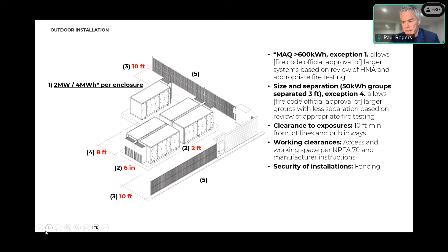And then as you can see, number five there is just showing a fence that is 10 feet. Now, I know there are some areas that have zoning, so the fence size should be based on your local zoning. But they want them at least 10 feet from the actual wall. They can go further than that based on what the code officials say, and they can back that up by using the UL 9540A test results. So you can go on to the next slide.